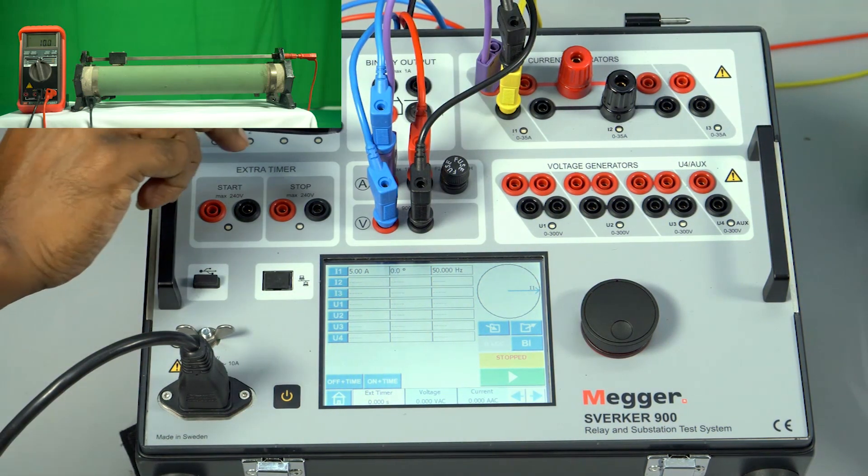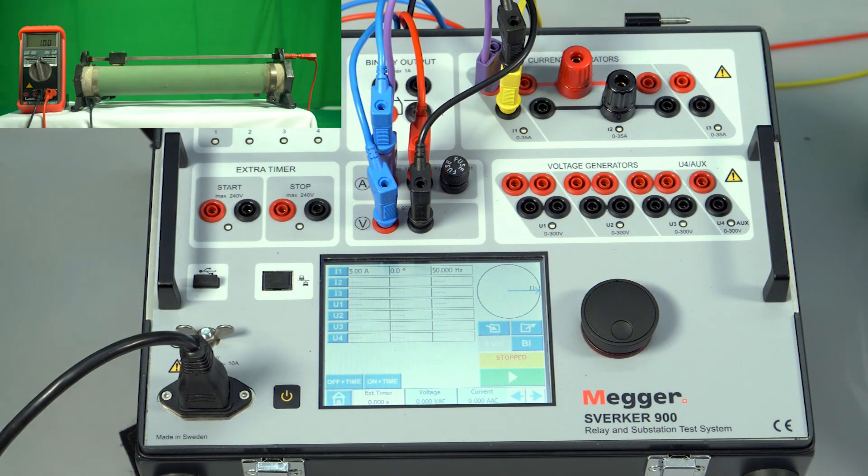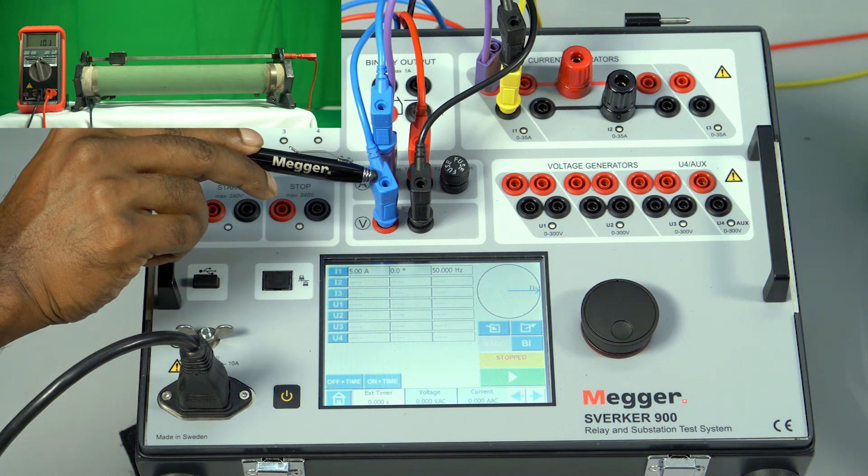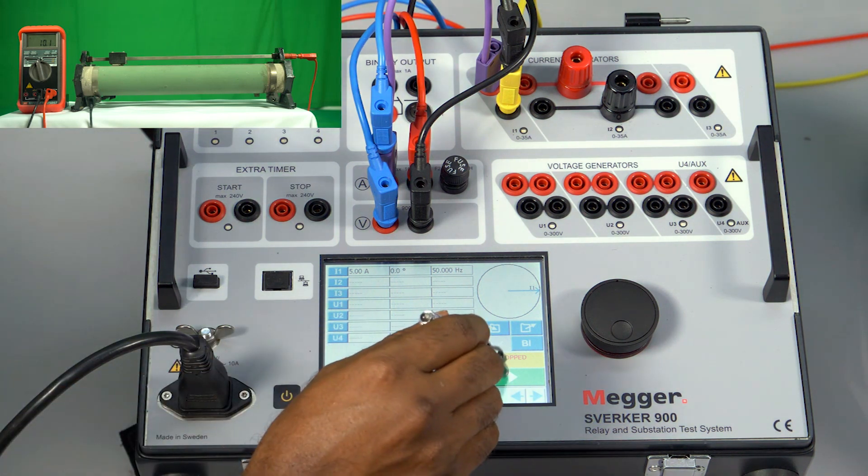The CT in series with the ammeter and the current is directly connected to the rheostat which is also connected in parallel to the voltmeter to verify the compliance voltage. Now let me inject 5 amps and stop the injection.